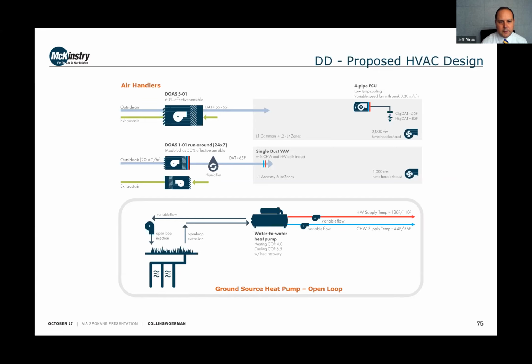That left us able to serve the remainder of the building with a rooftop dedicated outdoor air unit that brings ventilation air to each room and 4-pipe fan coils for space conditioning. This was chosen as the optimal combination of indoor air quality, regulatory compliance, acoustic performance, comfort, cost, and constructability.